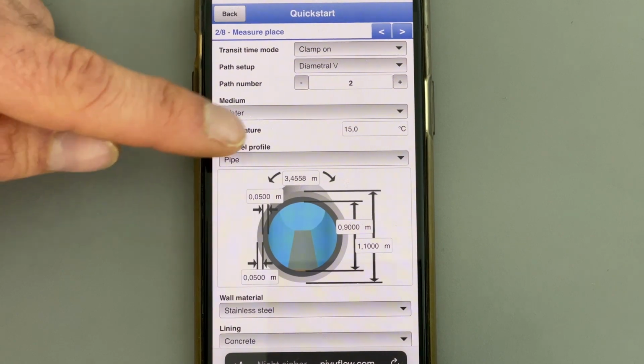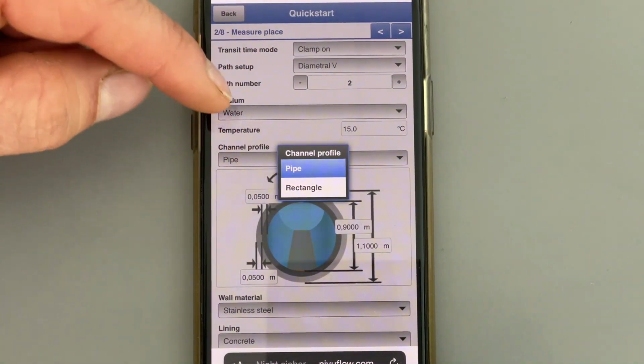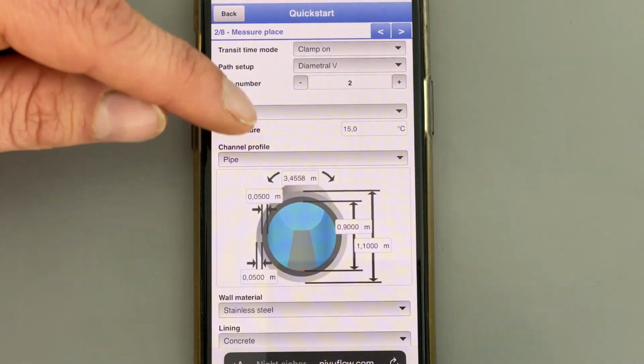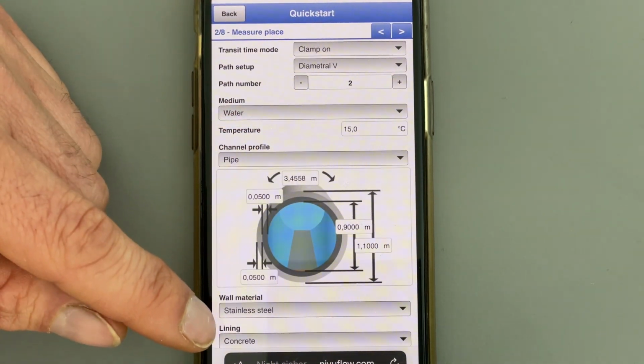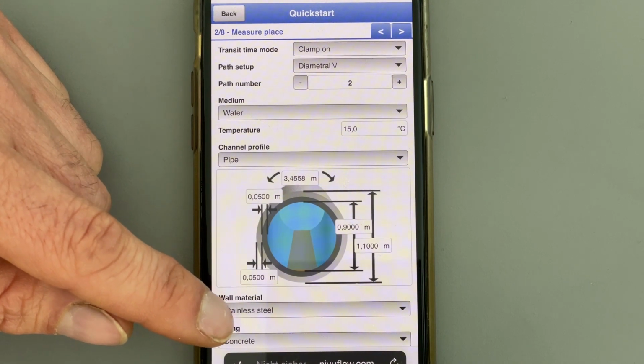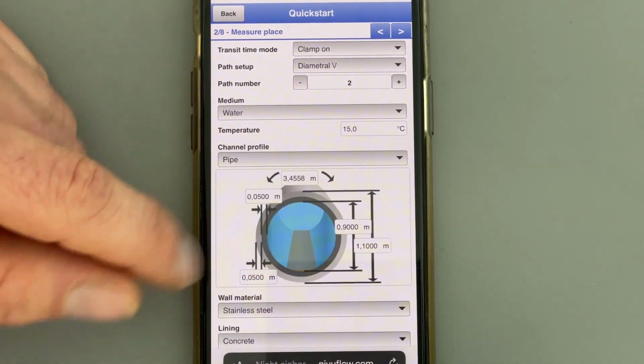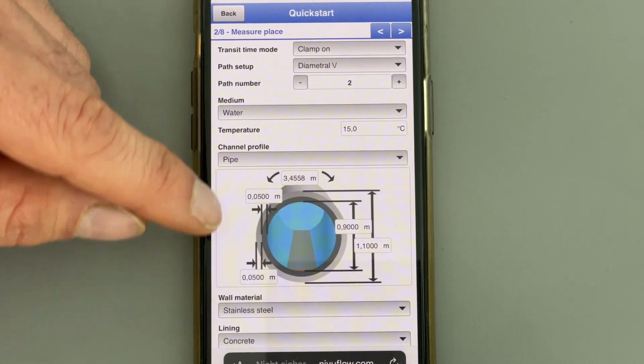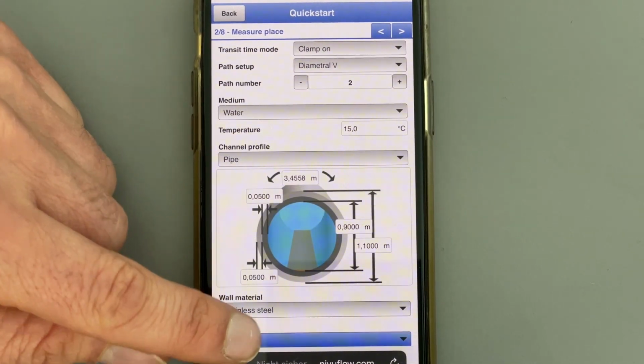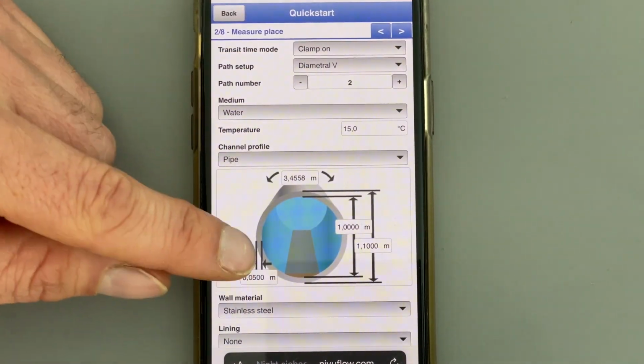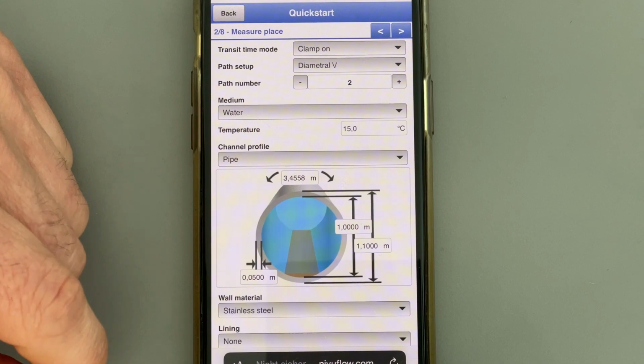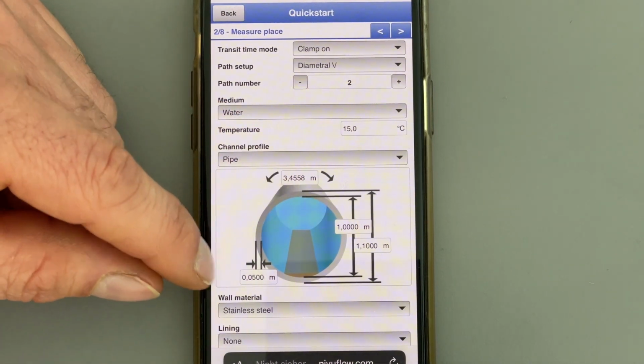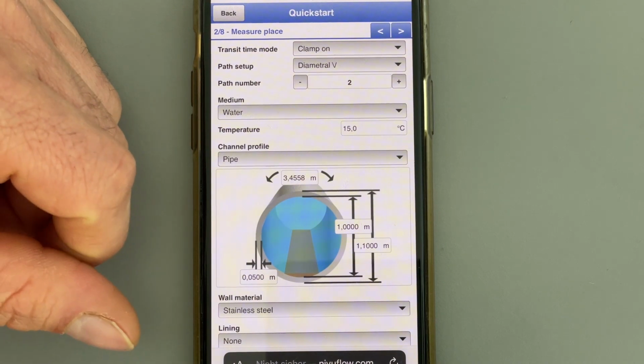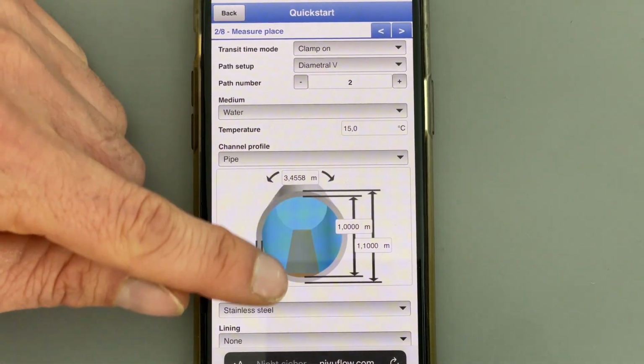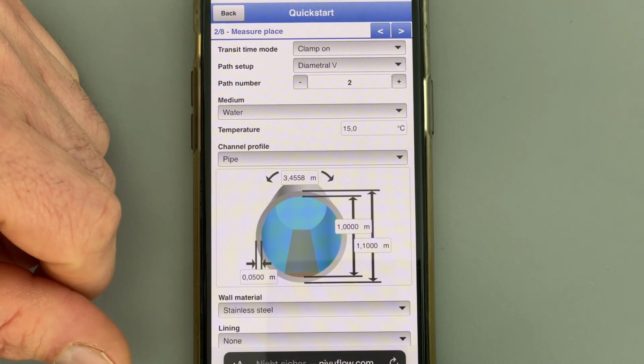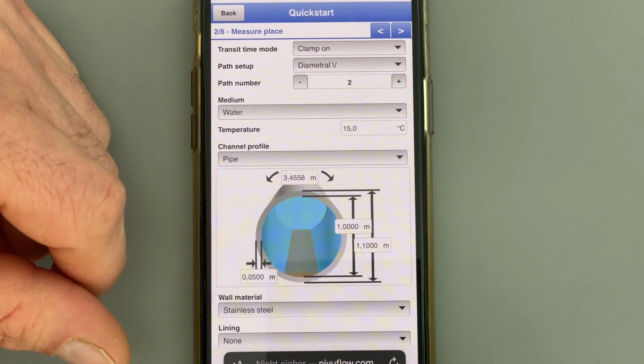Then the channel profile, you can choose between pipe and rectangle for sewer networks, for example, but in our case, pipe is always the right choice, the right geometry. And here in the setup of the pipe itself, you have this here because I have a lining. If I don't have a lining, you only use 2 parameters like the circumference of the pipe and, for example, the pipe wall thickness, and the other parameters like the inner diameter and the outer diameter will be calculated accordingly to the equation of a circle.